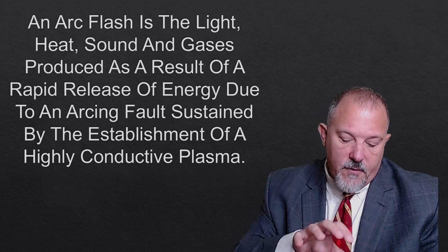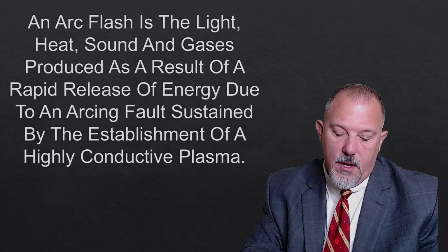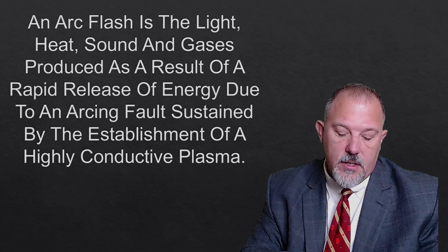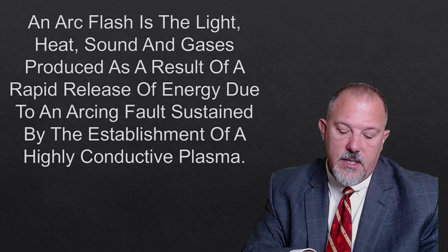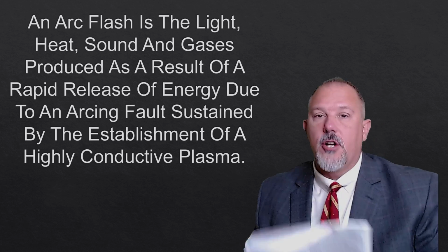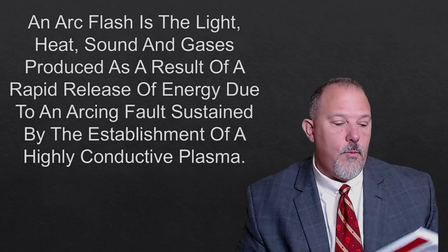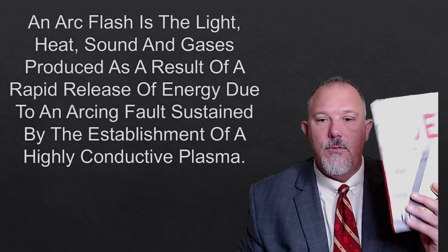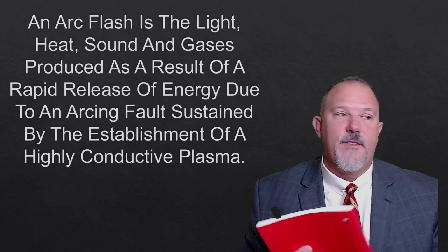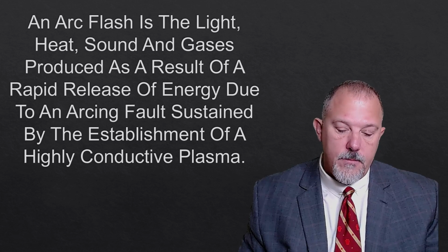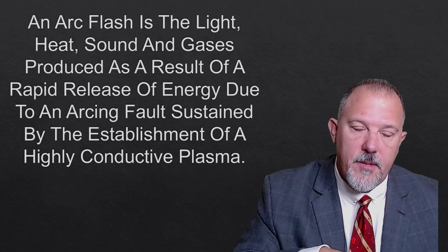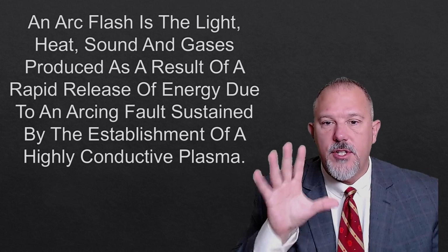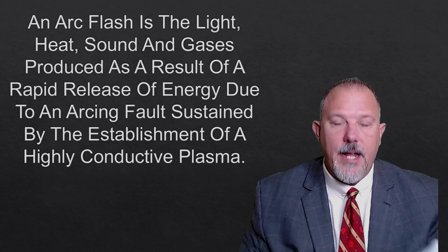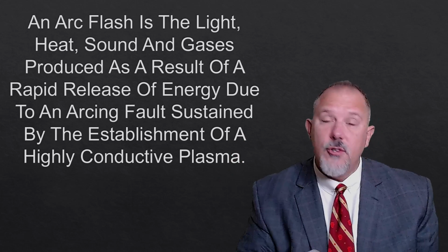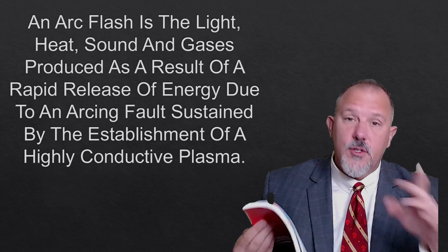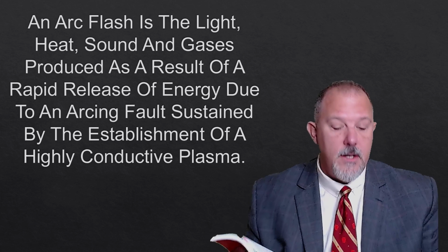All right, so there's two informational notes. The second note talks about 130.5(C) for examples of tasks that increase the likelihood of an arc flash incident occurring. And we're not necessarily going to get into 70E. That could be left for another day. But I wanted to go into this document primarily because we want to understand arc flash. And I think it's important to understand those two words, likelihood and severity, because you know what those two words are from. And I'm going to read it to you.